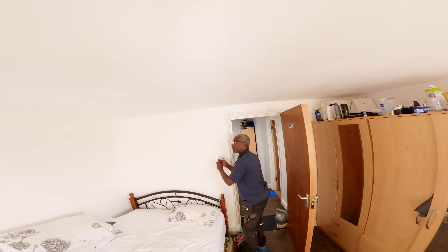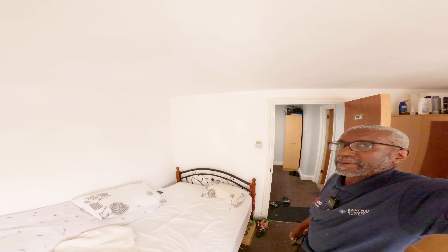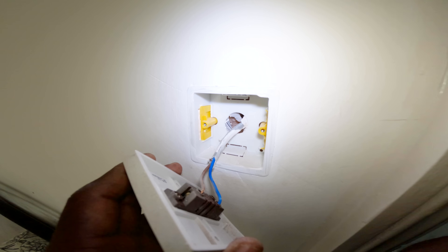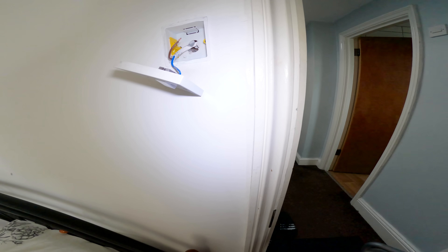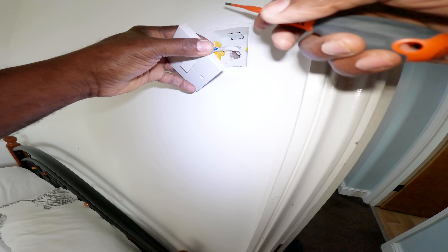This is the problem — if there are junction boxes that you can't see. They've only got one cable at the switch. Can't be a sparky who's done this, it's got to be... maybe they've done something. Because look — they've cut out the earth. That there is nicked, that's a bit too long, should be in more. This could be another case of the builder who's done the loft conversion, these people doing the electrics. It's always the way.